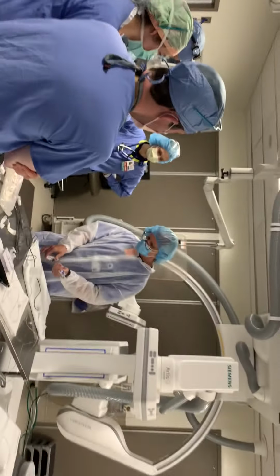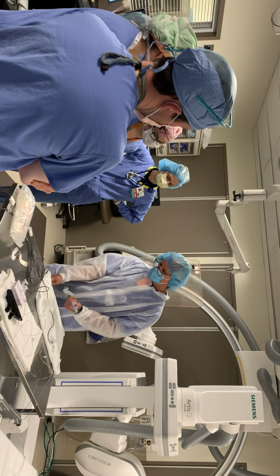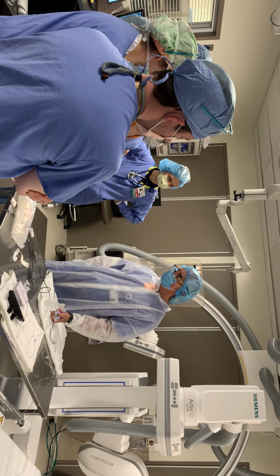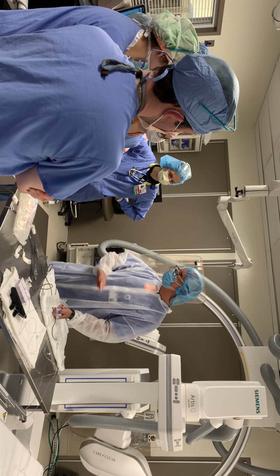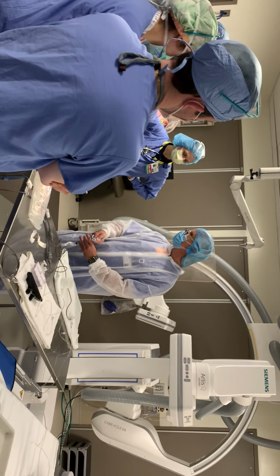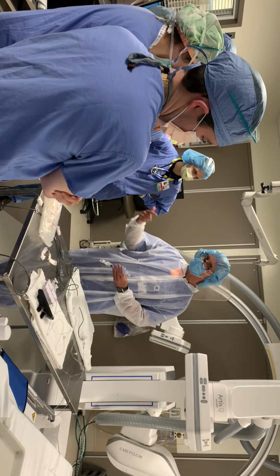Put your syringe on the back end. You just simply open it, flush out the end, turn that off, make sure you're connected with this open, 0. As soon as it's 0, you're going to close that, fix the 0, and now you can go on and off the pressure at will. The system works fantastic, gives you very accurate pressures, it's fast, it's easy to set up, extremely easy to troubleshoot.